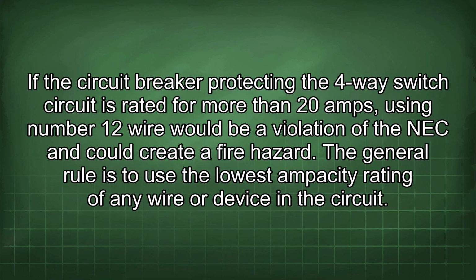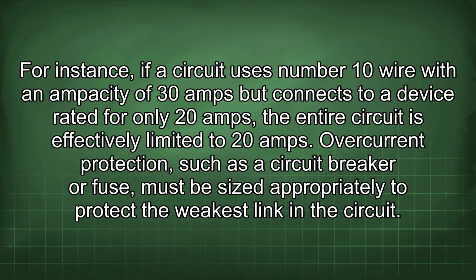If the circuit breaker protecting the four-way switch circuit is rated for more than 20 amps, using number 12 wire would be a violation of the NEC and could create a fire hazard. The general rule is to use the lowest ampacity rating of any wire or device in the circuit. For instance, if a circuit uses number 10 wire with an ampacity of 30 amps but connects to a device rated for only 20 amps, the entire circuit is effectively limited to 20 amps.